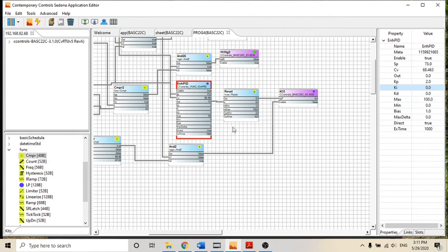I'm going to start warming it up by holding it in my hand. We'll see that the control value is going to start rising. Right now we're at dead band, and then we are going to require cooling. So cooling is true. We require cooling, and there goes my output, my damper, which is output number 3, that is receiving now 3.86 volts. So it would be opened for around 30-40%, and it goes opening more and more as we move along and as the temperature keeps climbing and climbing.